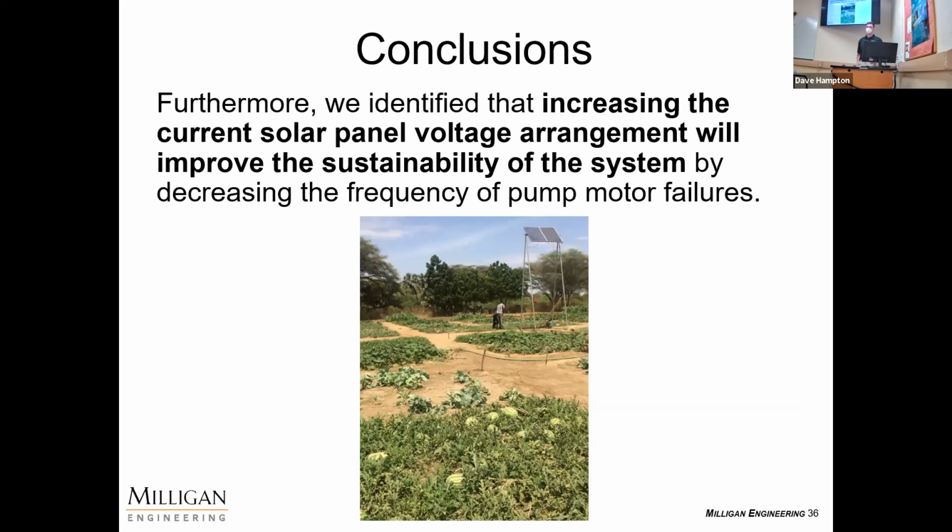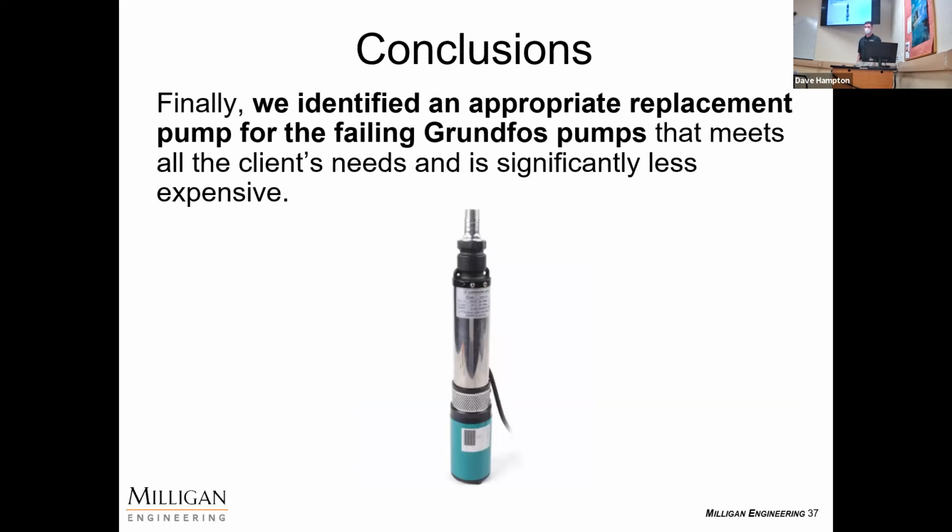Furthermore, we also identified that increasing the solar panels and increasing the voltage would improve the sustainability of the current systems by decreasing the frequency of the failures. And also, we identified an appropriate pump replacement that is significantly cheaper and meets all of our client's needs.